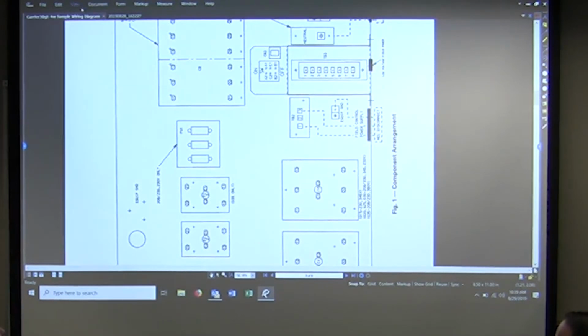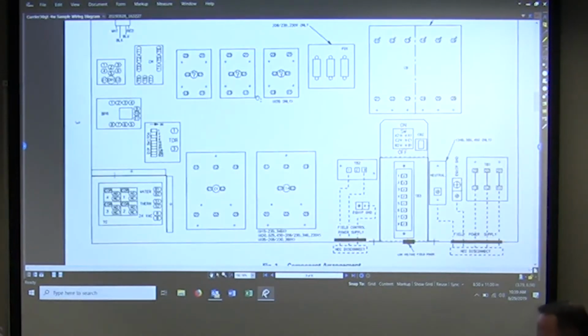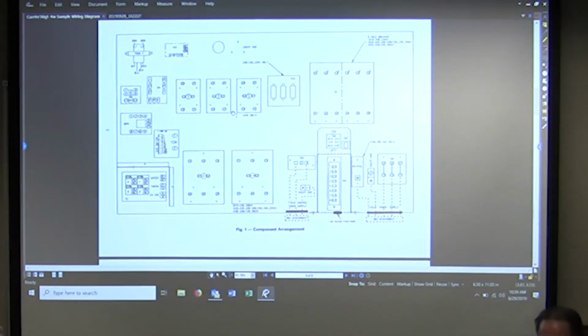We now have a layout on page, is it 3? Page 3 gives us a physical layout of the compartment. So when I open the door, this is how the pieces and parts should look as they're mounted inside of that opening. Okay, I have a circuit breaker up here, some fuses, this FC123 for fan contactors, C1, C1A for our compressor contactors. I have some terminal blocks down here, a switch that powers CB2 and a switch there.